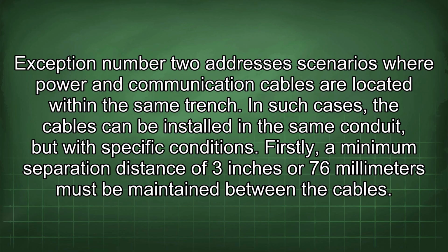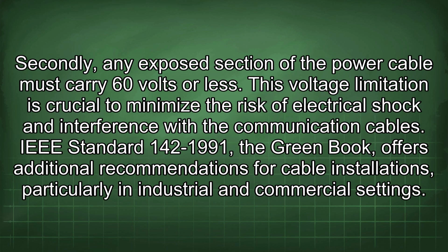Exception number 2 addresses scenarios where power and communication cables are located within the same trench. In such cases, the cables can be installed in the same conduit, but with specific conditions. Firstly, a minimum separation distance of 3 inches or 76 millimeters must be maintained between the cables. Secondly, an exposed section of the power cable must carry 60 volts or less. This voltage limitation is crucial to minimize the risk of electrical shock and interference with the communication cables.